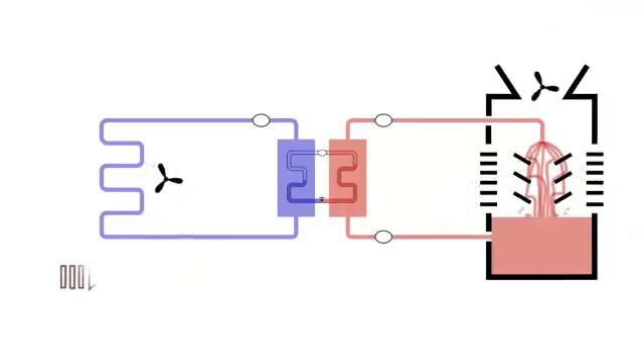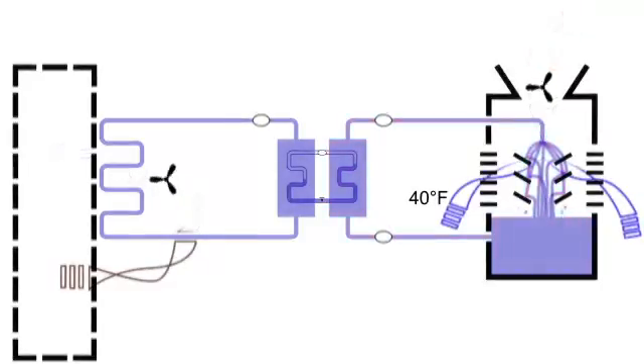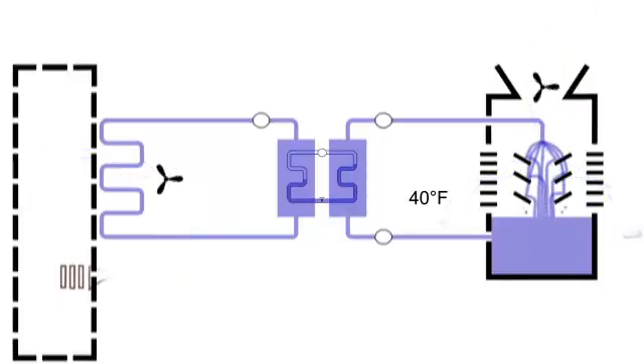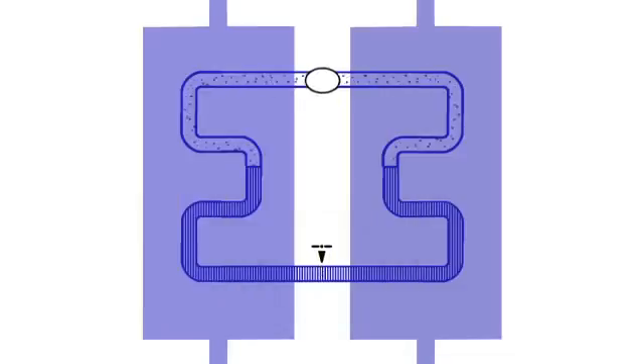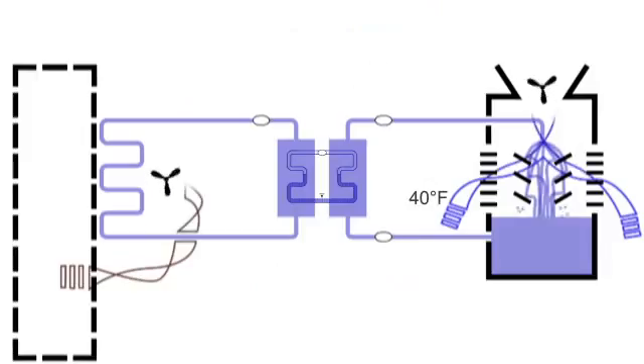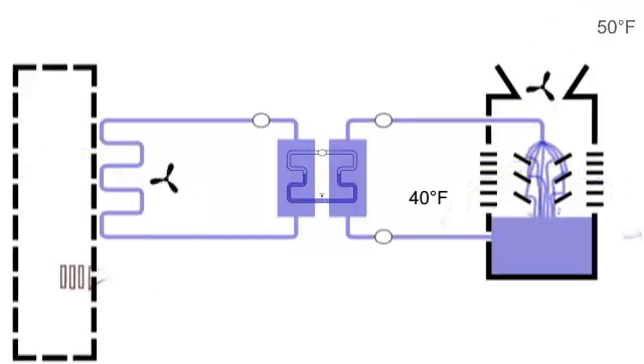In a water side economizer mode, cold air cools, and it really cools because it's winter, the water in the cooling tower. That cold water moves to the condenser side of the chiller and cools the coolant. The expansion valve opens, and this is important. The cooled coolant moves to the evaporator without fighting its way through the expansion valve. And there in the evaporator, it cools the chilled water. We've bypassed the compression refrigeration process entirely and still created chilled water for delivery in the standard way.